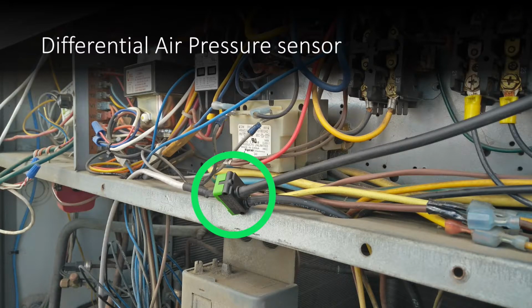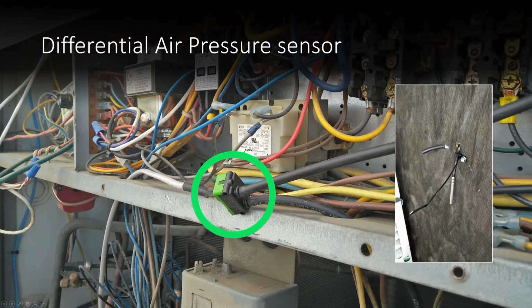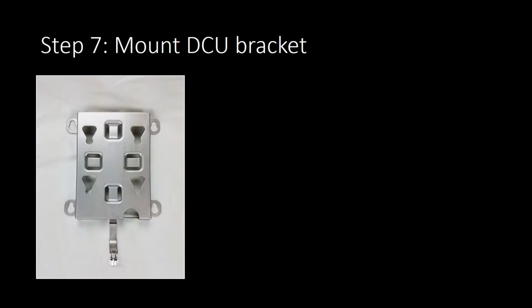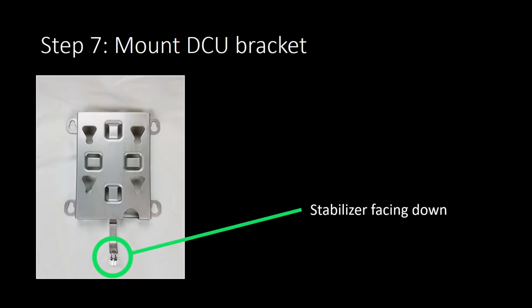The differential air pressure sensor has 2 ports for attaching tubing. Run tubing to either side of the air filter. Again, use fasteners to secure the tubing. As you install all sensors, use cable ties and screws to secure wires and tubing to ensure sensors stay in place. Step 7. Mount DCU bracket.